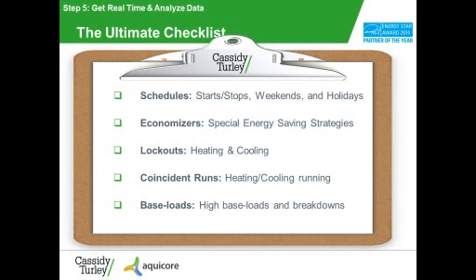But did we keep mechanical cooling off on that 51-degree day? Did we have electric heat locked out on that one December afternoon, or 2 December afternoons where it hit 72 degrees? Had we had that strategy in place? Did it happen in the building automation system? Did we see a drop-off in the use of electricity?